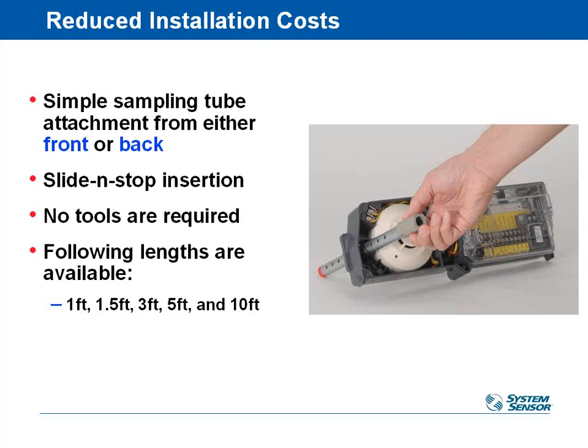The way to pick it is you have to pick one that's going to make it at least 80% of the way across the duct, and preferably 100%, but at least 80%. So if I had a 10-foot duct, I'd get a 10-foot tube. If I had an 8-foot duct, I would still buy a 10-foot tube, and then I would saw off the last 2 feet, so it made it through just the 8 feet of the duct. If I had a 6-foot duct, I could go ahead and get a 10-foot and cut 4 feet of it off, or I could buy a 5-foot and put it in, because it's going to make it about 80% of the way across the duct. So I have that flexibility choice.